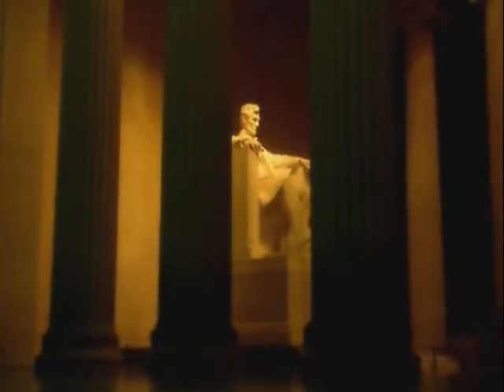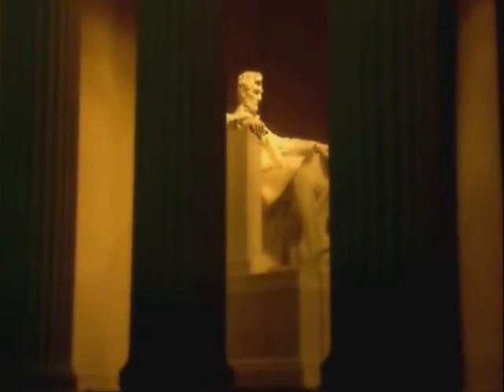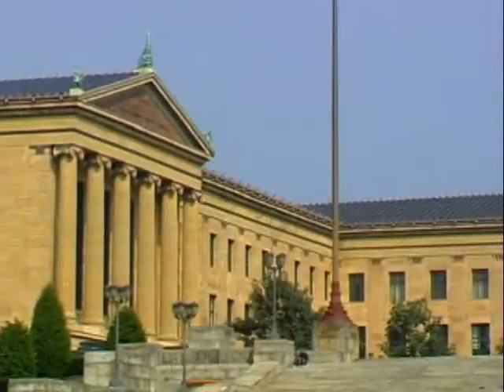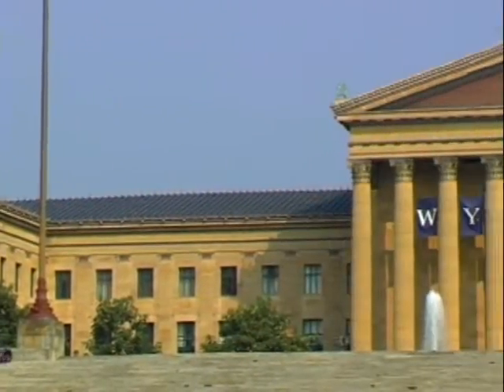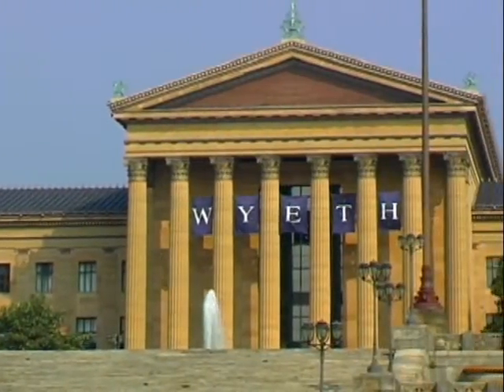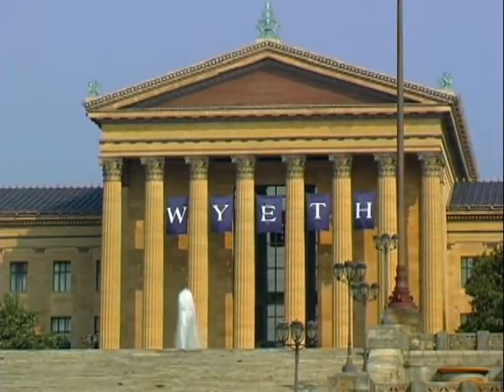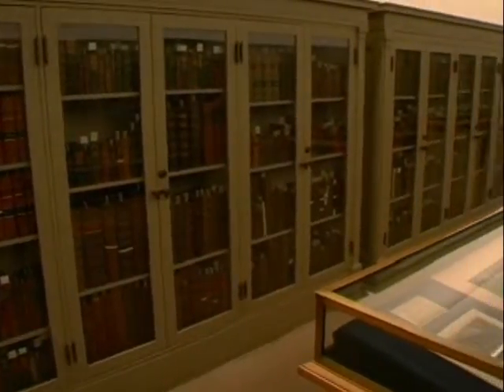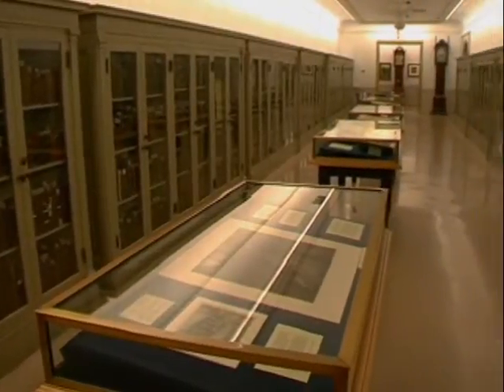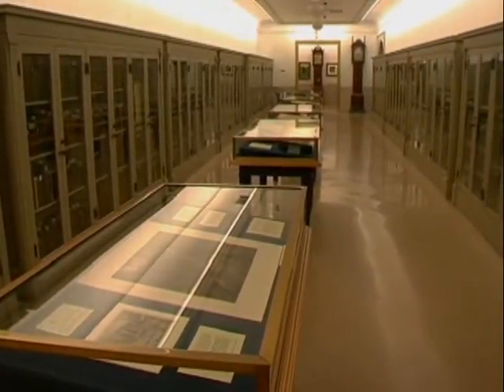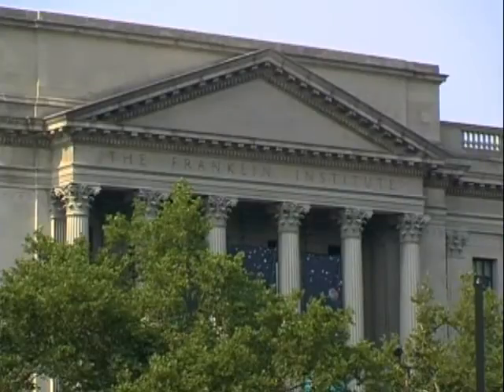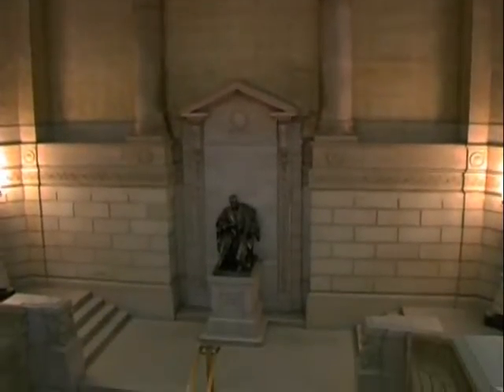equipment. If the area to be protected houses historical or scientific artifacts, they could be ruined by water, dry powders, and other chemical-based fire suppression systems. Consider the result if a gallery of fine priceless art is deluged with water or liquid-based extinguishing agent. The damage caused by the fire suppression agent could be as destructive as that caused by the fire itself. The building would be saved, but could you afford the loss of a computer or an irreplaceable historical document?